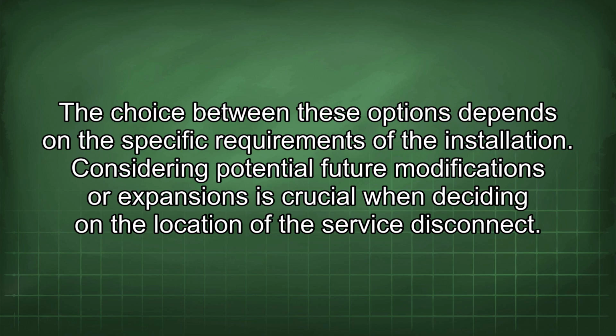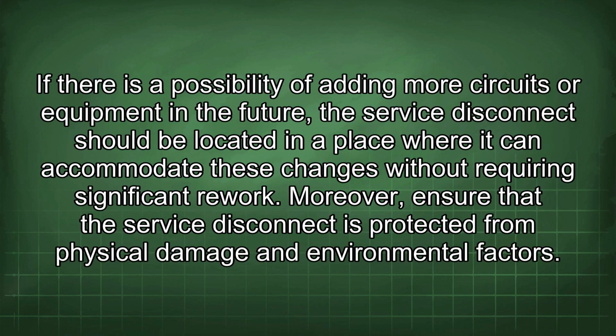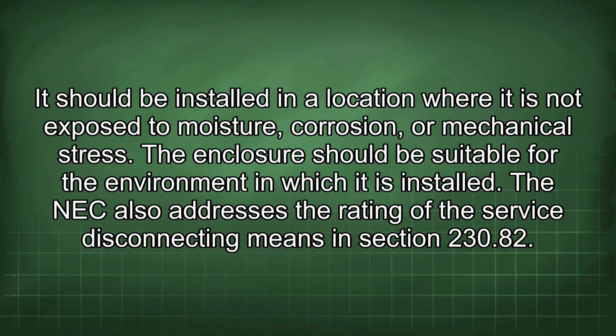Considering potential future modifications or expansions is crucial when deciding on the location of the service disconnect. If there is a possibility of adding more circuits or equipment in the future, the service disconnect should be located in a place where it can accommodate these changes without requiring significant rework. Moreover, ensure that the service disconnect is protected from physical damage and environmental factors. It should be installed in a location where it is not exposed to moisture, corrosion, or mechanical stress. The enclosure should be suitable for the environment in which it is installed.